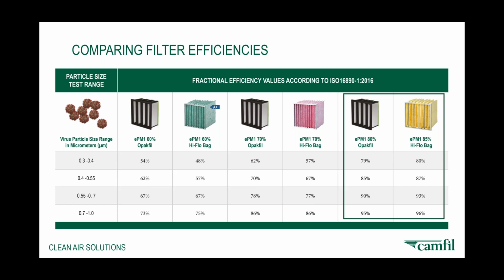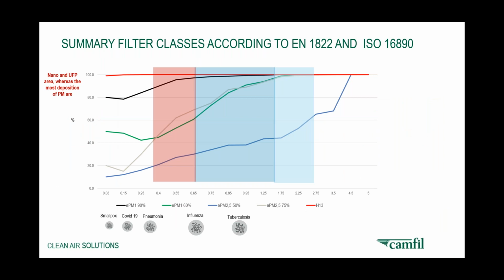If we look at it in a different way and look at the summary of the filter classes according to both EN 1822, which is the HEPA filter testing standard, and ISO 16890, which we discussed very briefly earlier on, you can see that as the viruses or the particle sizes decrease, it's more difficult to capture them with the various type of filter. So if you're looking at an ePM1 90% on the bottom, right through to a H13 filter, you can see that your H13 or HEPA filter is the most effective at capturing those small particle sizes. And we look at the properties of filtration to work out or give you a quick understanding as to why that is.